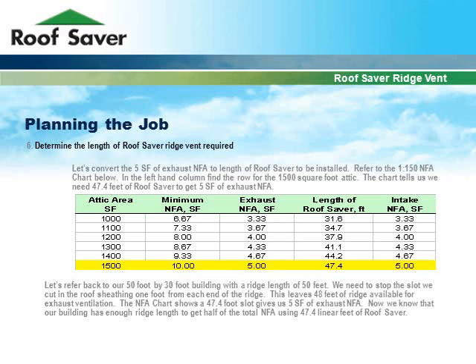Let's convert the 5 square feet of exhaust net free area to the length of Roof Saver to be installed. Refer to the 1 to 150 net free area chart. Find the row for the 1,500 square foot attic; the chart tells us we need 47.4 feet of Roof Saver to get 5 square feet of exhaust NFA. For our 50 foot by 30 foot building with a 50 foot ridge, we stop the slot one foot from each end, leaving 48 feet of ridge available. The NFA chart confirms that a 47.4 foot slot gives us 5 square feet of exhaust NFA, so our building has enough ridge length.